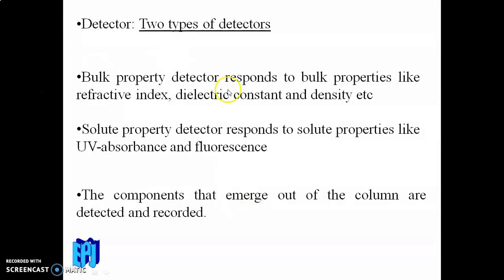There are two types of detectors. The bulk property detector responds to bulk properties of the solution such as refractive index, dielectric constant, and density. The solute property detector responds to properties of the solute itself, such as UV absorbance and fluorescence — useful when components contain chromophores or auxochromes. The components that emerge from the column are detected and recorded.